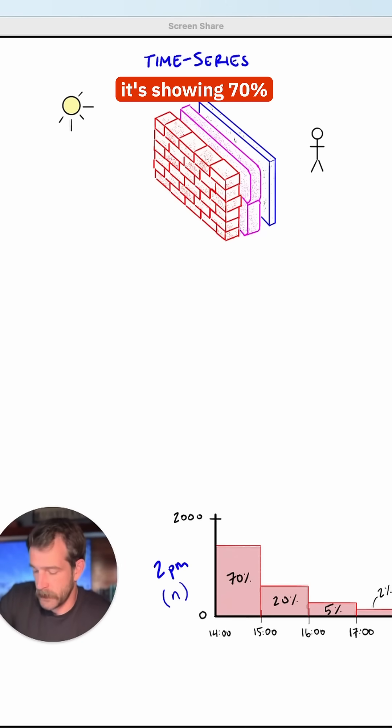So for this wall assembly, it's showing 70% will be transferred in the first hour, 20% in the second, 5% in the third, and so on. So at 2 p.m., we'll call it in. 70% of that 2000 BTU total will enter the space. That comes out to 1400 BTUs.